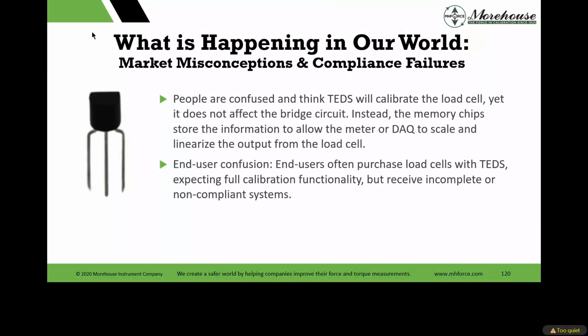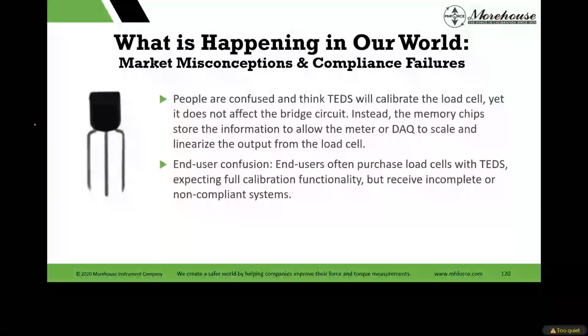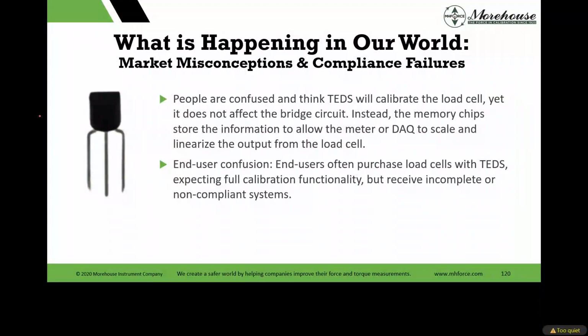People tend to think TEDS will calibrate, and are confused, thinking TEDS will calibrate the load cell, but it doesn't do anything. It's just a little EEPROM chip. It's like a USB, for lack of a better understanding; it's a little more complicated than that, but it's a USB that has some memory on it that someone programs in a lab, and then the meter typically reads these two span points and converts that digital signal into a numeric pounds force, kilonewtons, newtons, kilograms force, whatever you're reading. That's all it does. And end users often purchase load cells with TEDS expecting this full calibration functionality, but they receive incomplete or non-compliant systems.